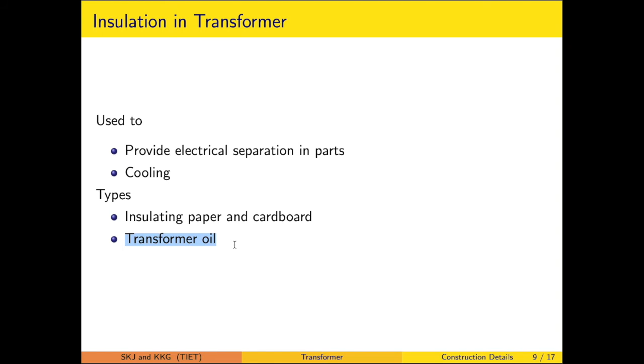Now the operation of the conservator, breather and the Buchholz relay has to be understood, but these components are typically part of the large power system, not of the small or moderate rating transformer. Previously we discussed that the transformer has the highest efficiency, ranging from 98 to 99%. But when the size or the rating of the transformer increases, even 1 or 2% losses result in a very huge amount of heat. Because of that heat generation, there will be an increase in the temperature of the transformer oil, and it will experience expansion, and when the temperature reduces, it will experience contraction.